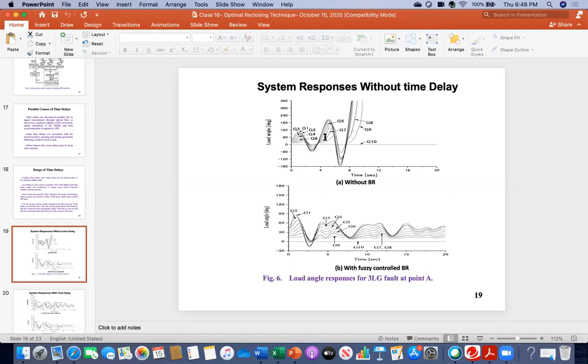If I look only until 5 seconds, I was not sure whether it would come back or go unstable. So I increased it to 20 seconds, and then I noticed that around 10 or 11 seconds, all generators were going out of step.